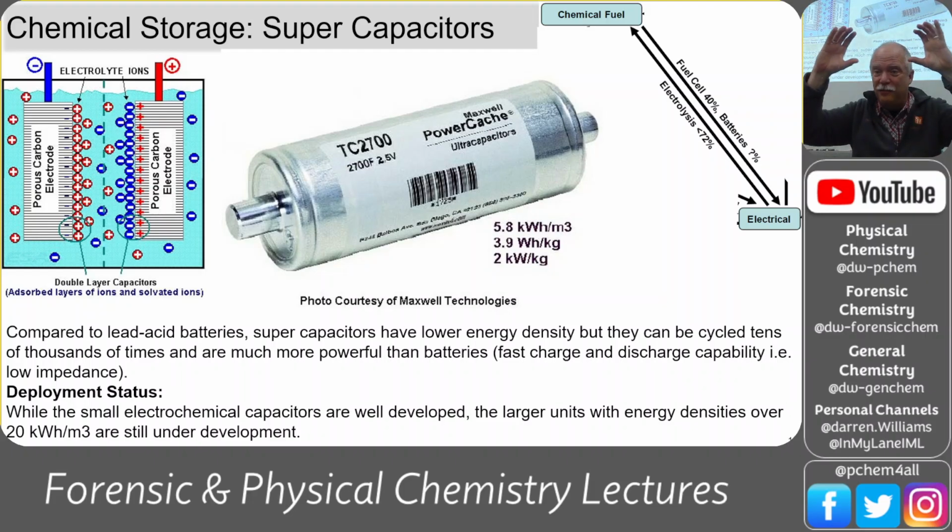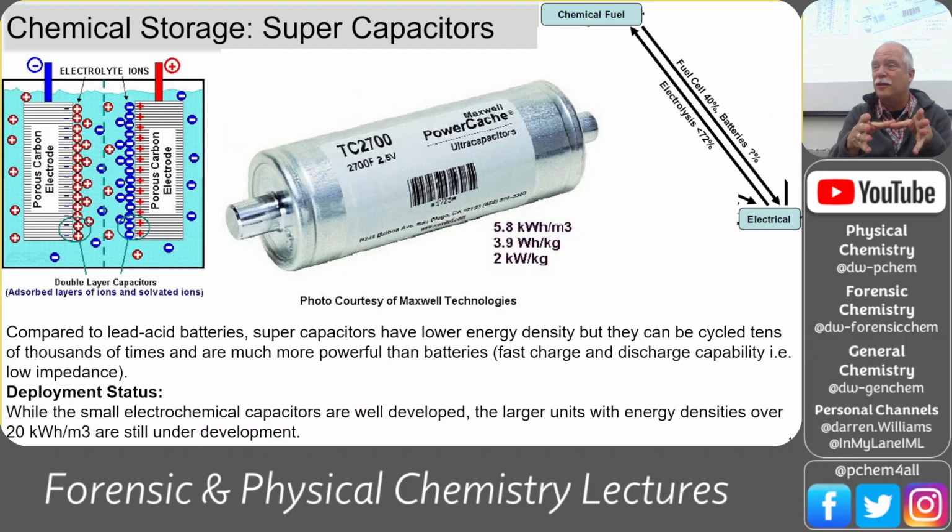So when a sign says high voltage, no entry, those signs are for real, because you could unplug it from the wall and it could still have enough electricity in the capacitors to kill you. The very first thing you did, if you had to do any maintenance inside this cabinet, was to ground out the capacitors. And that was always the job of the new person in the lab.